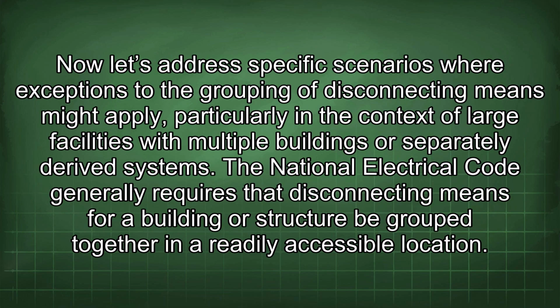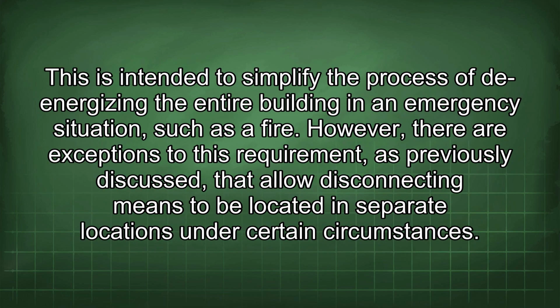Now let's address specific scenarios where exceptions to the grouping of disconnecting means might apply, particularly in the context of large facilities with multiple buildings or separately derived systems. The National Electrical Code generally requires that disconnecting means for a building or structure be grouped together in a readily accessible location. This is intended to simplify the process of de-energizing the entire building in an emergency situation, such as a fire. However, there are exceptions to this requirement, as previously discussed, that allow disconnecting means to be located in separate locations under certain circumstances.